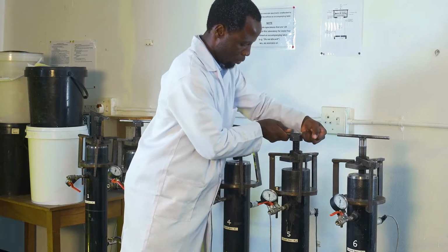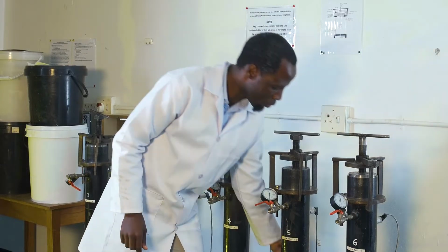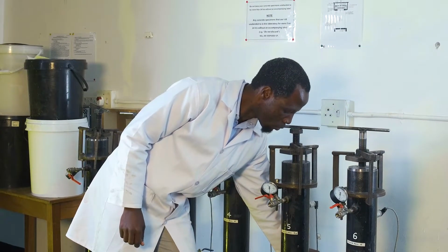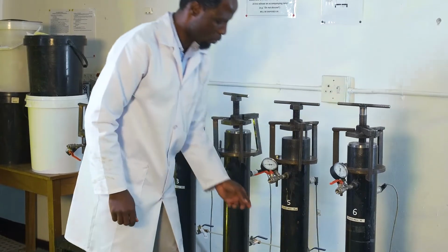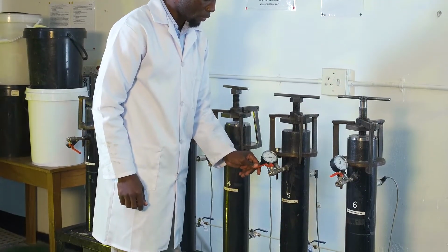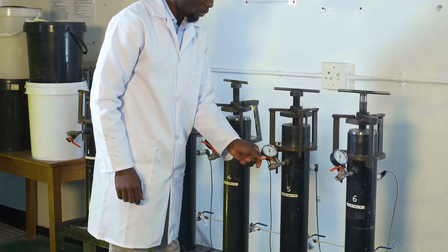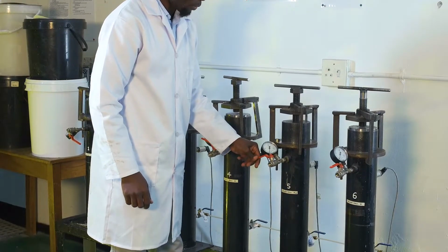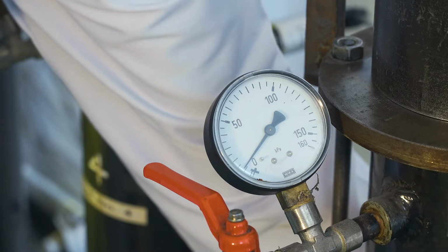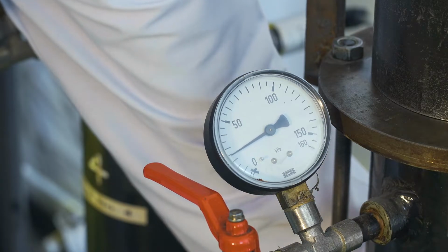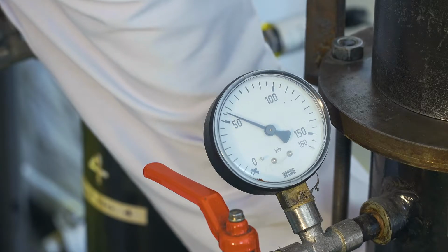With both the inlet and outlet valves open, allow the oxygen gas from the supply cylinder to flow in and out of the gas chamber for about 5 seconds. This will force out air contained in the gas chamber to ensure that only oxygen gas is contained in the gas chamber. After 5 seconds, close the outlet valve and let the pressure in the gas chamber rise to about 100 kilopascals before closing the inlet valve.